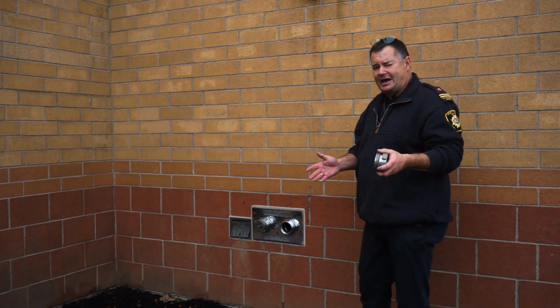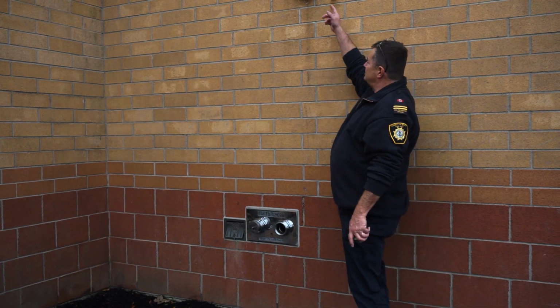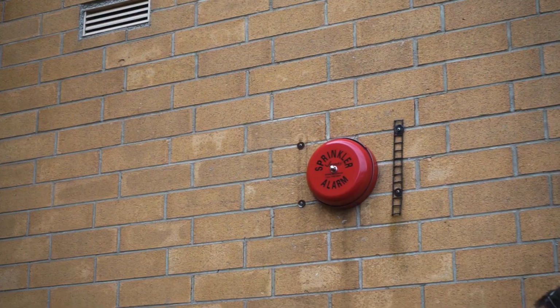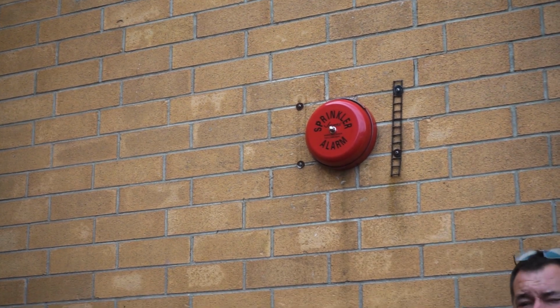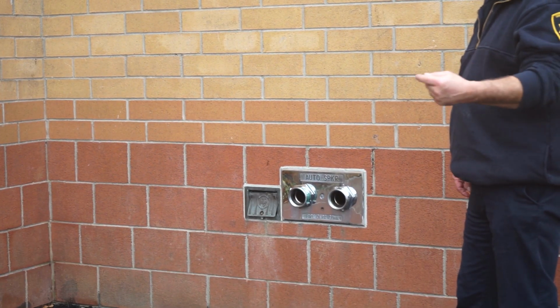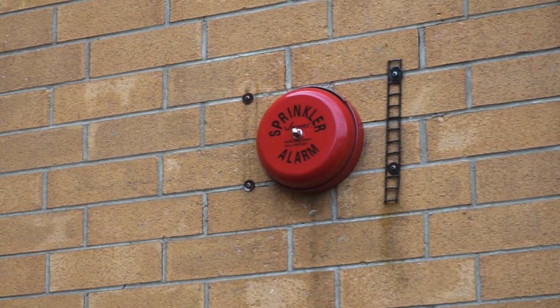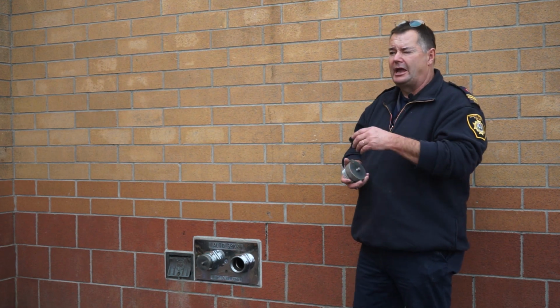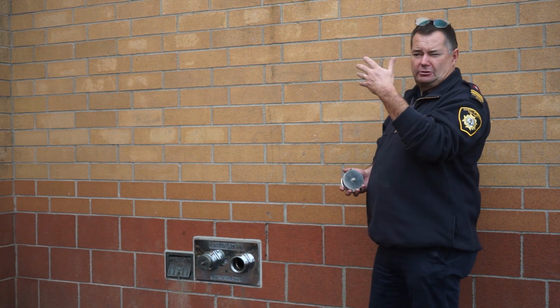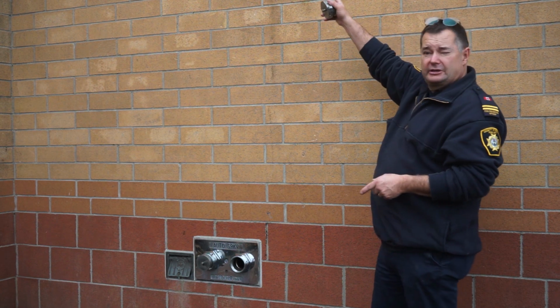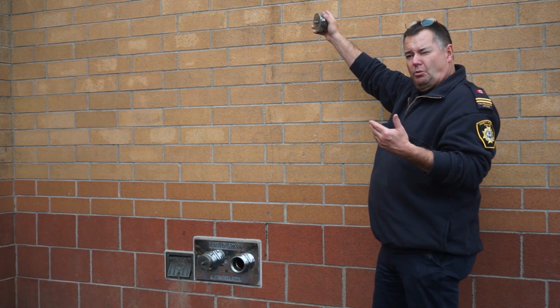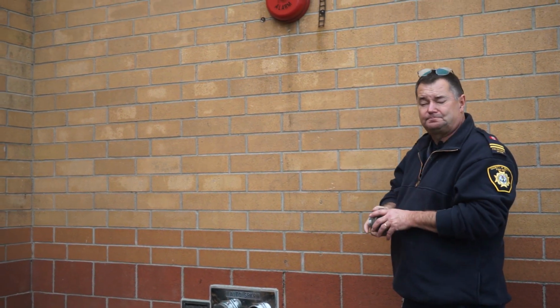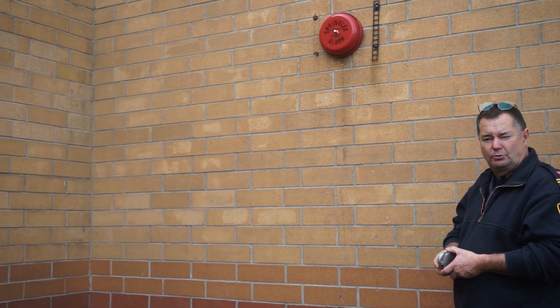But before all of this happens, if a fire was to occur, this little bell up here is called a sprinkler alarm. When there's any kind of water flow through the fire sprinkler system, this bell sounds. The reason this bell sounds is for the neighbors in the community around the building. If we ever are out for an evening, whether we're at a restaurant or taking the dog for a walk, and you walk by an industrial or commercial building, and you hear this bell ringing and you don't know why, that could be a sprinkler alarm, and it might be a good point to call 911.